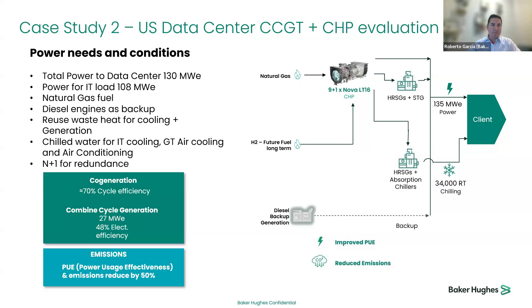Some takeaways and conclusions: first, data center sizes are increasing every day, and for these bigger sizes, new technologies need to be considered. Gas turbines for base power are being considered for data centers bigger than 50 megawatts, from 50 up to 300 or 400 megawatts. Data centers are looking to improve their PUE numbers, getting close to 1, and to reach that, they definitely need to consider the use of combined heat and power.